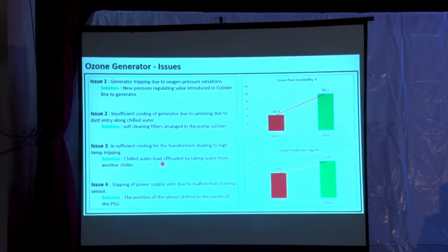And also insufficient cooling for the transformers. We have power supply units, and for that we have a transformer. There we maintain the cooling system. For that also we operate from a different chiller to get a continuous supply of chilled water without affecting the ozone generation. One more thing is tripping of the power supply units due to malfunction of the temperature sensor. In the PSU, the ambient temperature is maintained by the AHU.